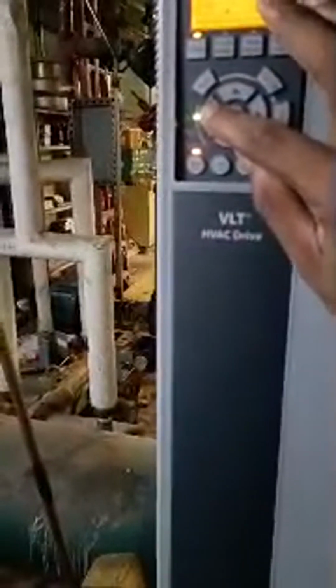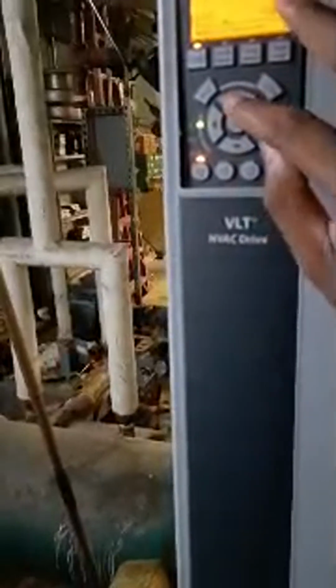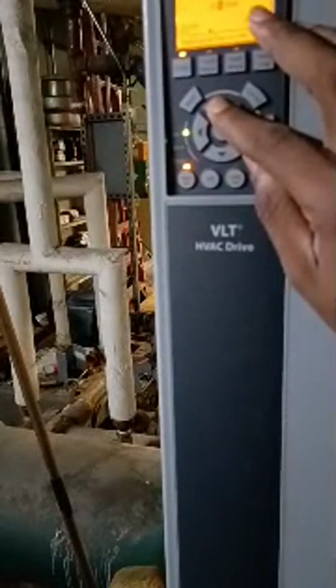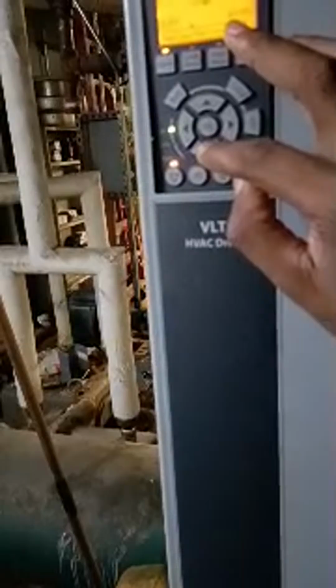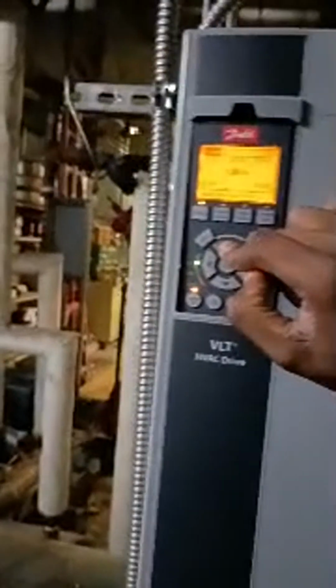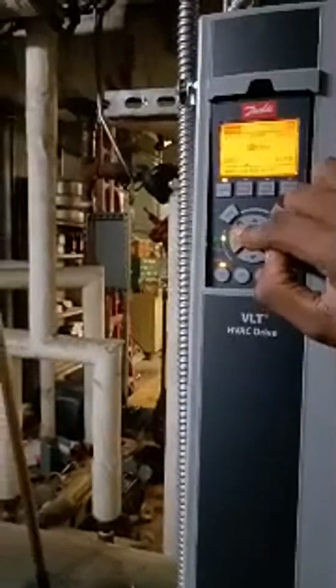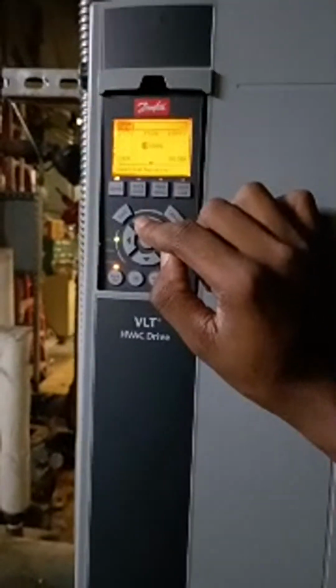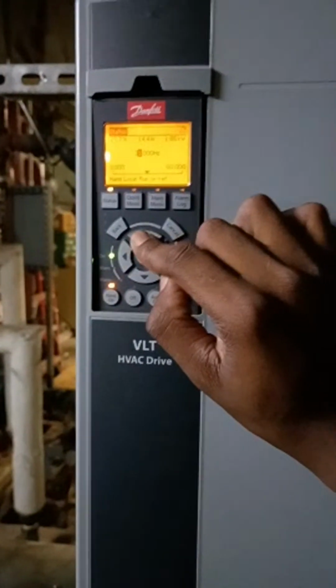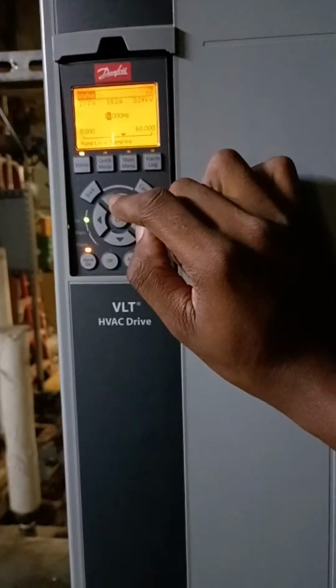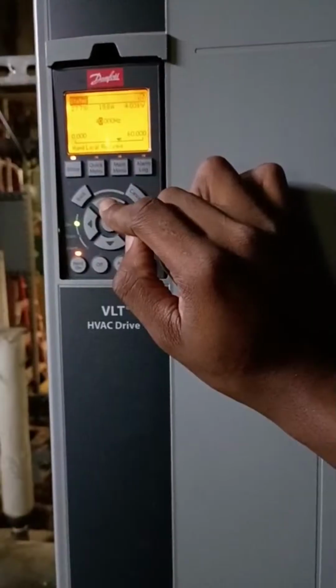All right, so the most important one is the chill water one. I'm going to put it in hand. Okay. Let's put this at 0. Actually, just go up on this. Start moving this up. So all we're doing is ramping this motor up so that when we turn the chiller on, it can slowly make its way towards flow. We don't want to mess up the flow on the chiller.